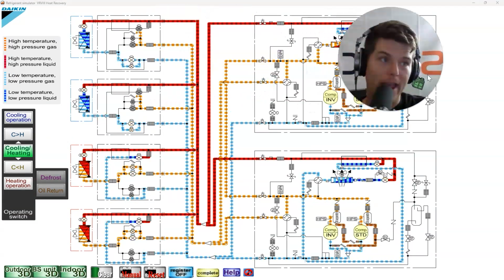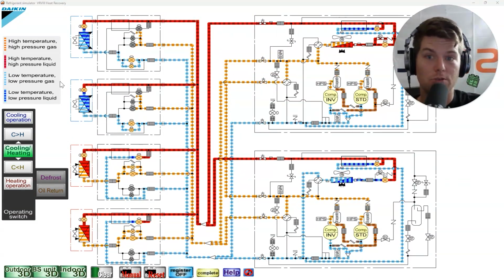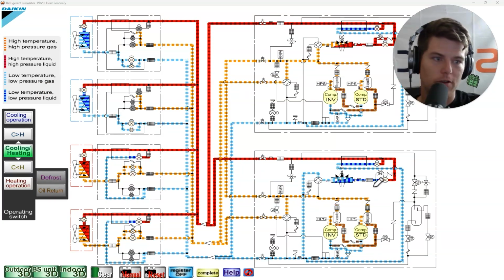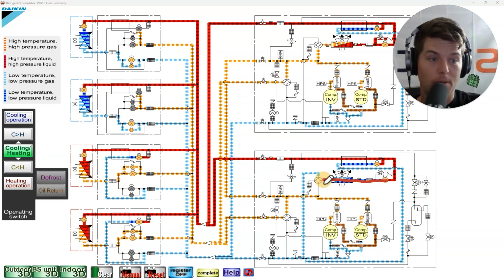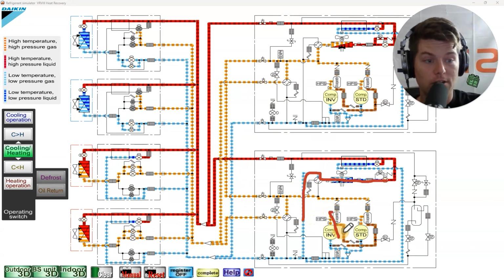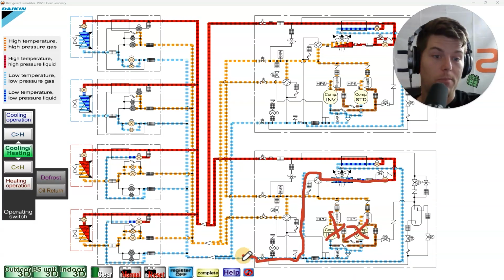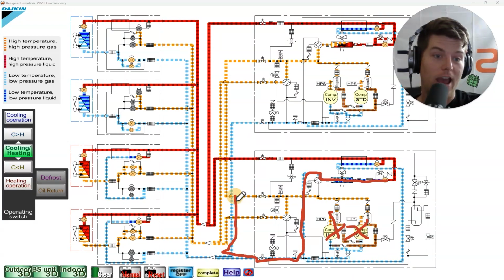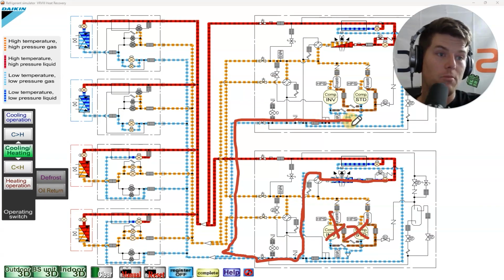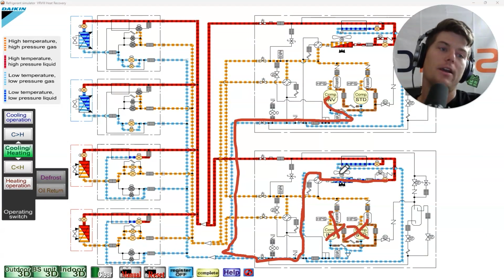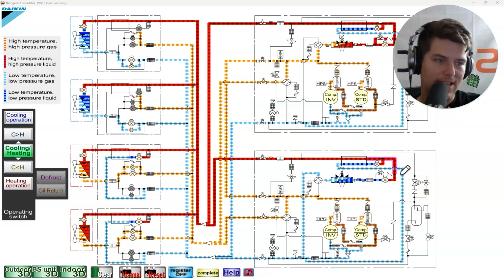When does that go away? Well, when that module is actually being used to create hot gas and the four-way valve shifts over. So now it's doing this. It's dumping liquid refrigerant, but guess what? None of these compressors are operational. These 2 are dead. So what's happening? It's going back down like this, and it's going up and over to the other module where refrigerant is actually flowing. This is the path that the liquid refrigerant is taking currently.